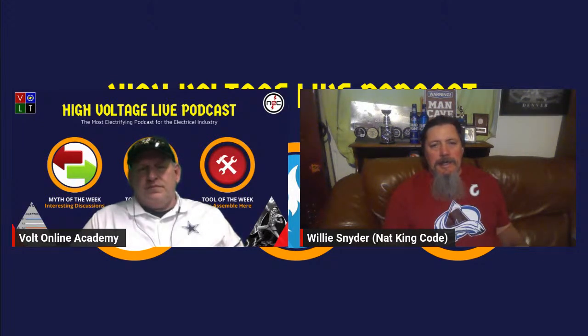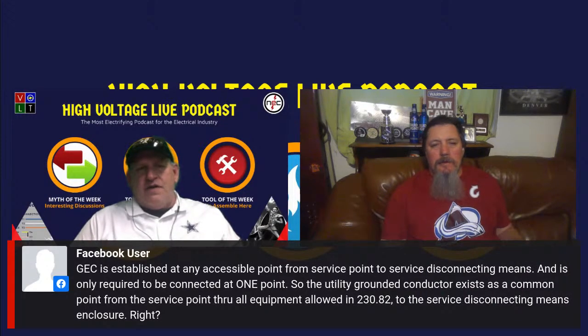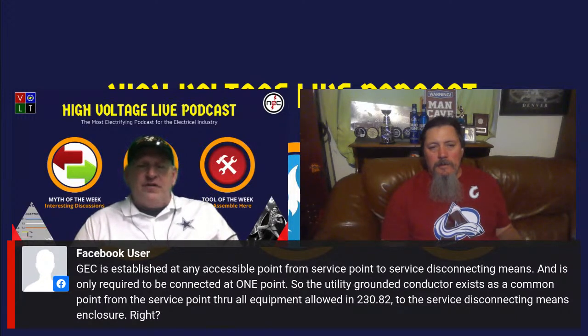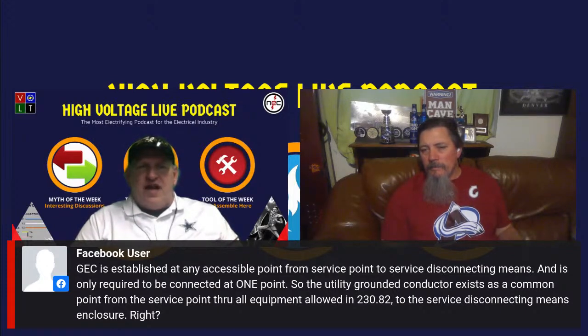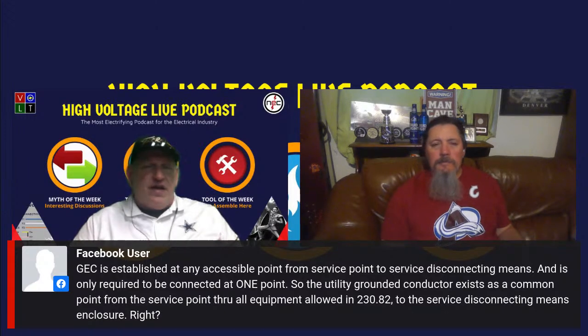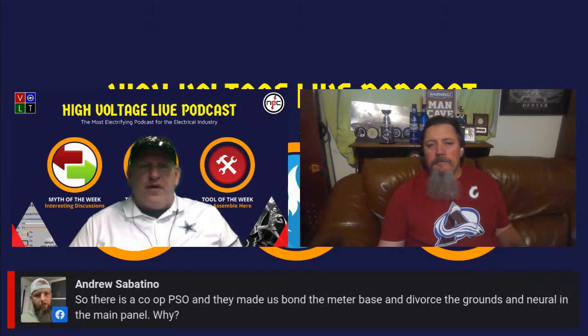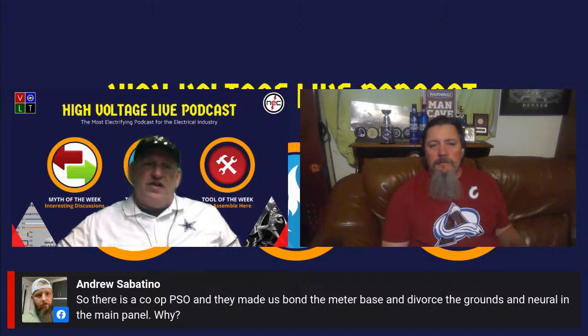Your emergency disconnect is on the supply side. Well, now, if you don't have overcurrent protection, all of that is considered on the supply side. And that's what I'm saying. Right. You have to establish where the supply side is, and that's what Justin and I were talking about. I feel that once you establish that overcurrent protection, that's your first disconnecting means, everything on that is load side at that point. But if there's no overcurrent protection at the source equipment, now everything is considered on the supply side.